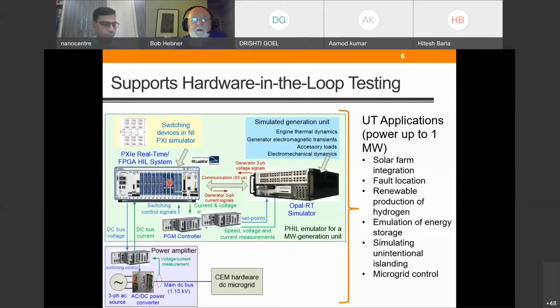This system can operate at speeds appropriate for modern power electronics, simulating their behavior down at the 5 to 10 nanosecond range. It communicates back to the Opal RT at 50 microsecond speeds, which gives us the influence on the grid for whatever the power electronics are doing at their own speed. So we can model and simulate the power electronics separately, yet it's intimately connected to what the rest of the grid is doing.